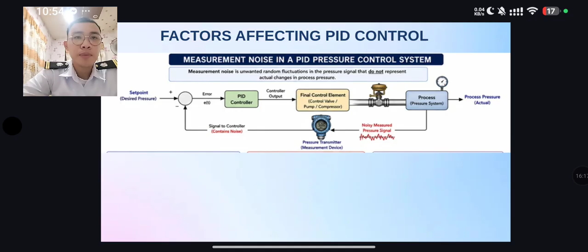Next, here's the comparison of clean signal versus noisy signal. With a clean signal, the measured pressure closely follows the actual pressure, allowing the PID controller to maintain stable and accurate pressure control. On the other hand, with the noisy signal, the measured pressure fluctuates even when the actual pressure is stable, causing unnecessary actions by the control valve, pump, and compressor. This can also reduce efficiency and cause unstable operation.